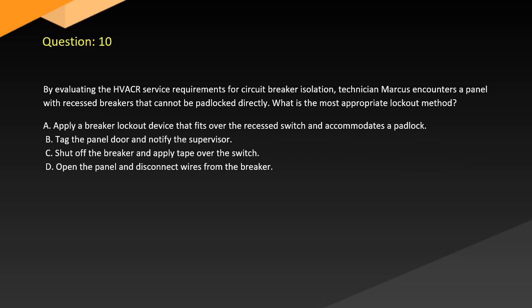Question 10. By evaluating the HVACR service requirements for circuit breaker isolation, technician Marcus encounters a panel with recessed breakers that cannot be padlocked directly. What is the most appropriate lockout method? A. A breaker lockout device that fits over the recessed switch and accommodates a padlock. B. Tag the panel door and notify the supervisor. C. Shut off the breaker and apply tape over the switch. D. Open the panel and disconnect wires from the breaker.